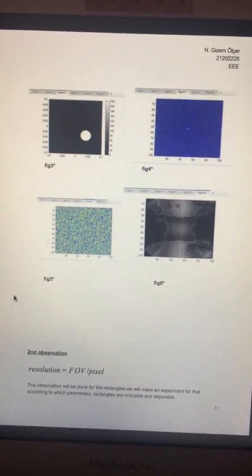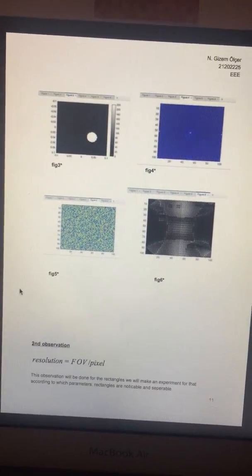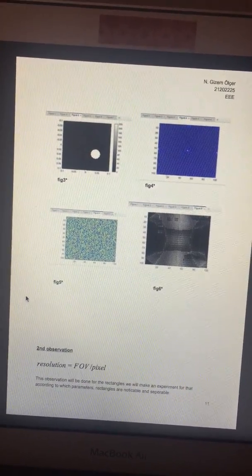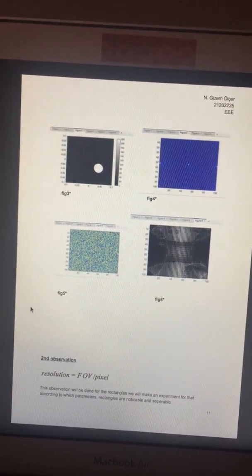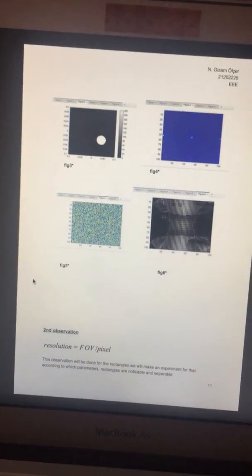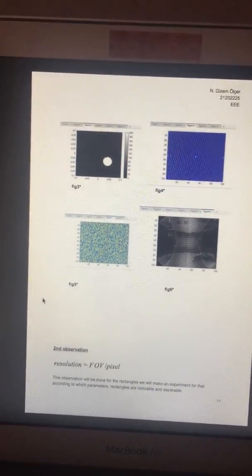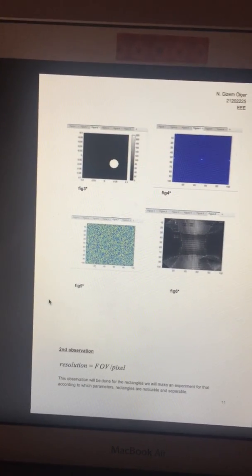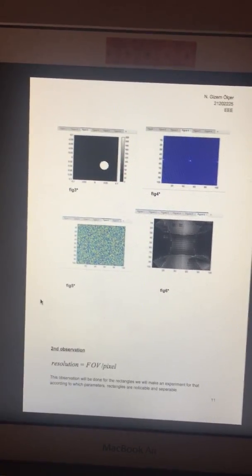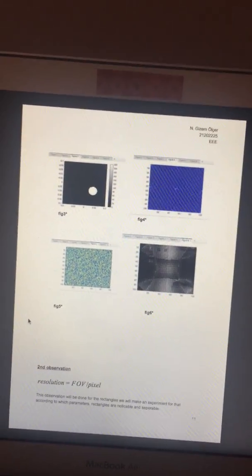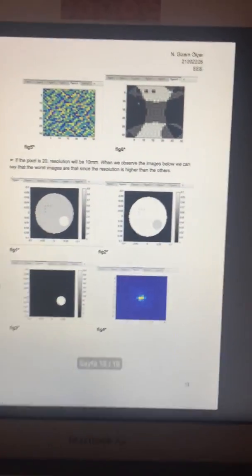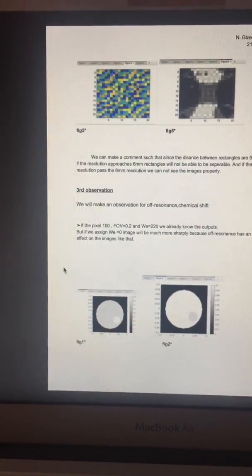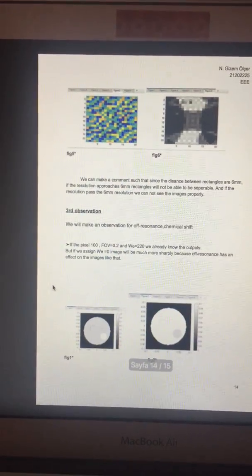The second observation is about resolution. We will observe according to which parameters a rectangle can be noticeable and separable. When we decrease the pixel, rectangles will not be able to be seen easily. While resolution approaches the six millimeter, which is the gap between the rectangles, they cannot be separable. And if resolution passes six millimeter, we cannot see the images clearly.